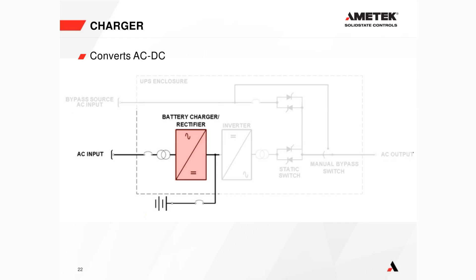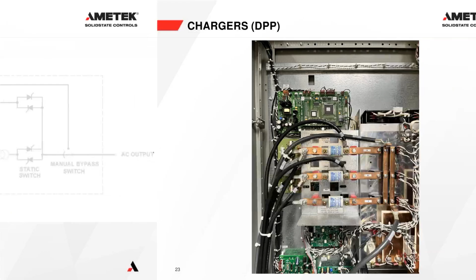Now we're going to talk about the battery charger rectifier. You can see it highlighted here in the single line drawing, inside our 10 kVA UPS. This is very simplistic, but this is actually how it works. We have our three phases going in, I'll call them A phase, B phase, and C phase. If you measured between this bus bar here and this bus bar here, with a 120 volt nominal battery, you'd measure about 130 volts AC phase to phase. So A, B, C is our input to the rectifier bridge.